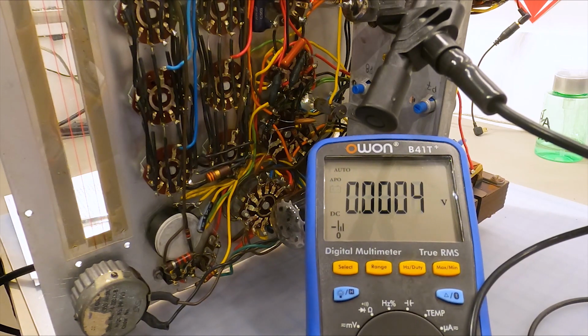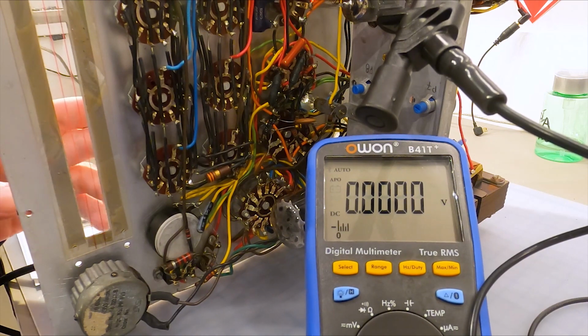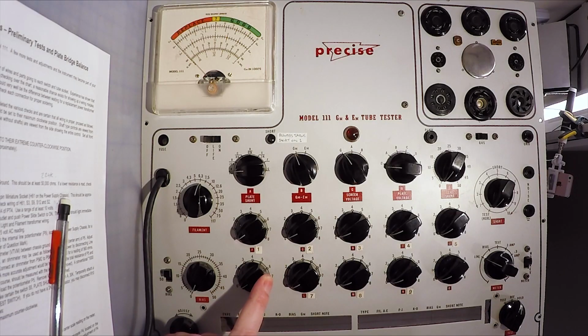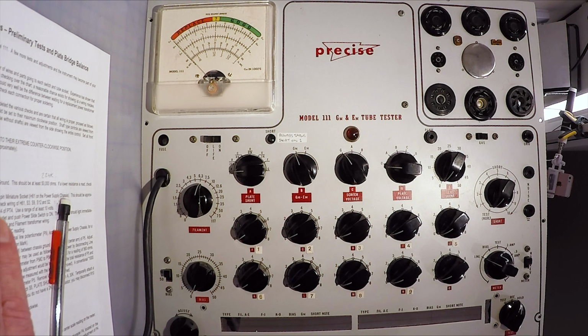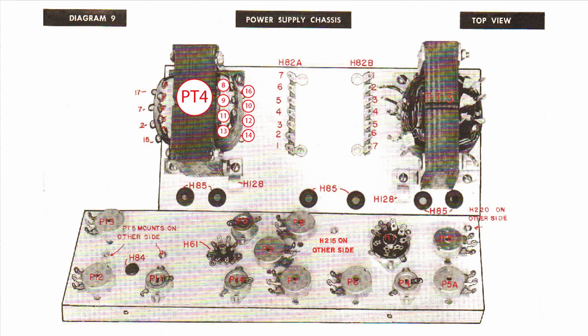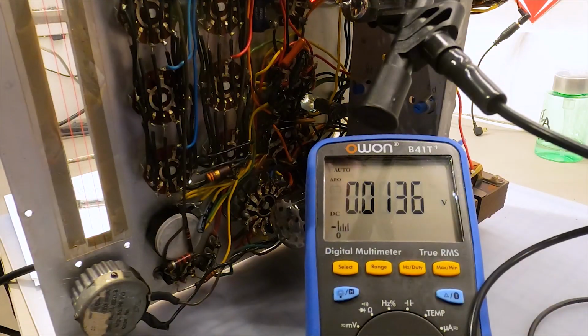And I have done the wiring check indicated in the calibration instructions and have adjusted all of the controls to their full counterclockwise position. The test switch is on hold. The line pot is on the middle position. The meter slide switch is to normal. The bias slide switch is to 10 volts. The off/line/on switch is to off. That's this switch right here. And we're going to check the resistance from terminal number 16 of the power transformer PT4 to ground. And we're looking for at least 50,000 ohms.